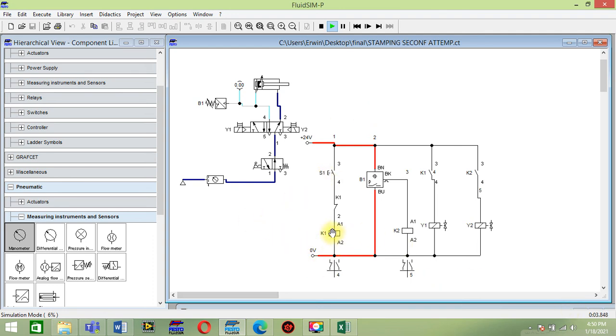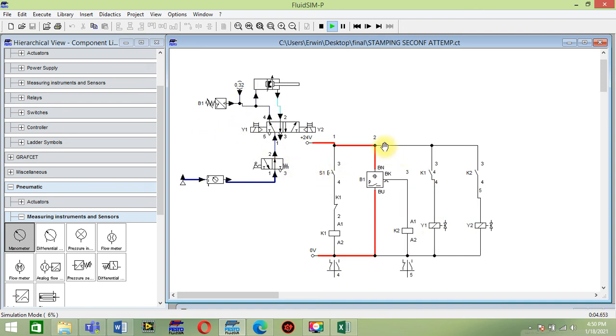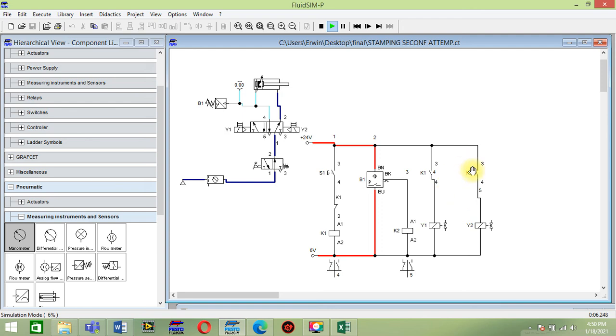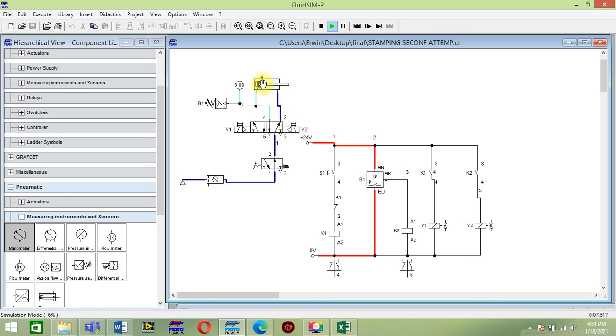Just remember, K1 is for this K1 switch, then K1 is for Y1, then Y1 is for this solenoid. When we activate this, supply will go through this and through this. When it reaches the limit of 0.8 MPa, the sensor B1 will activate and will supply K2, then K2 will supply Y2. Y2 will supply this solenoid, then push using the pressure. It will go through Y2, then it will retract the cylinder.